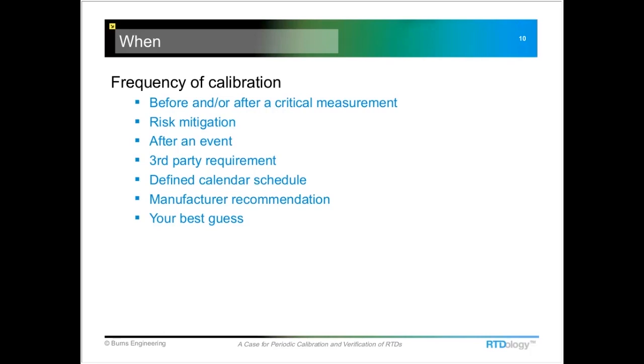You may have an event happen, where there might have been some water hammer going in a pipeline, for example. That can cause a temperature probe to drift, so you may want to do a calibration at that point. You may have that third-party watchdog again, with some kind of requirement that you have to do it at least so often. And then the manufacturers can give you some idea, based on the process, of what the frequency is for a calibration. Some people will just pull the calendar out and say, well, we've got to do it every 6 months, and that's where you start. And then if you don't see any changes with that, we might be able to extend that interval for calibration.